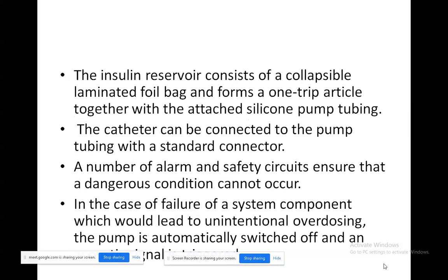The insulin reservoir consists of a collapsible laminated foil bag and forms a one-trip article together with the attached silicone pump tubing. So the insulin reservoir is like a tank-like material, that is, the plastic cartridge, which consists of a collapsible laminated foil bag. It is like a layer, and it forms a one-trip article together with the attached silicone pump tubing. Have you understood? Collapsible laminated foil bag means it is a layer laminated in the reservoir, forming a one-trip article which will be attached to your pumping device.